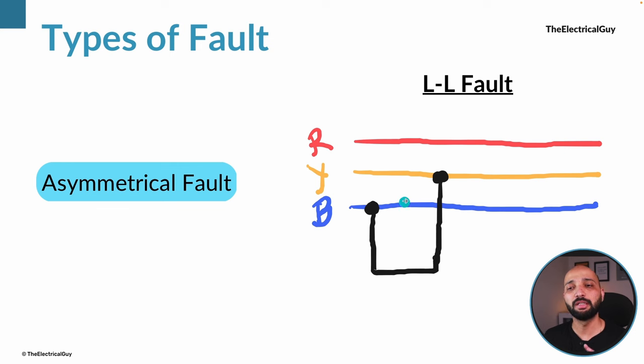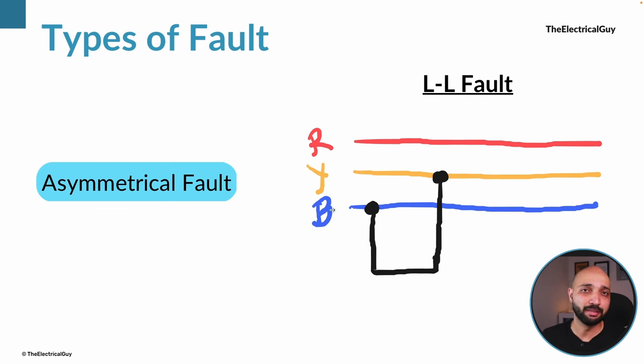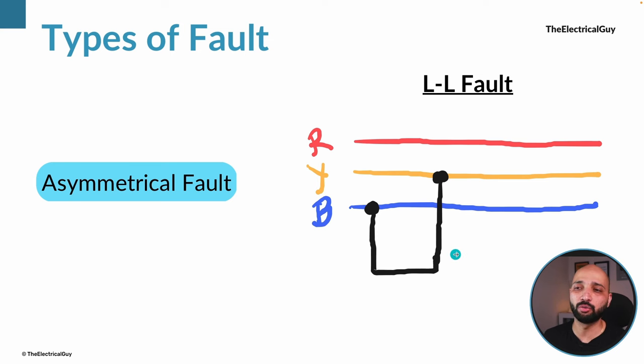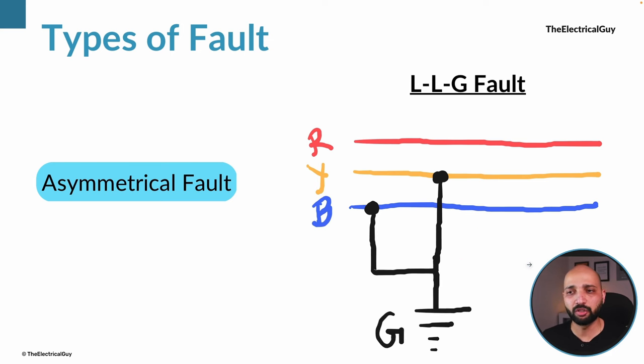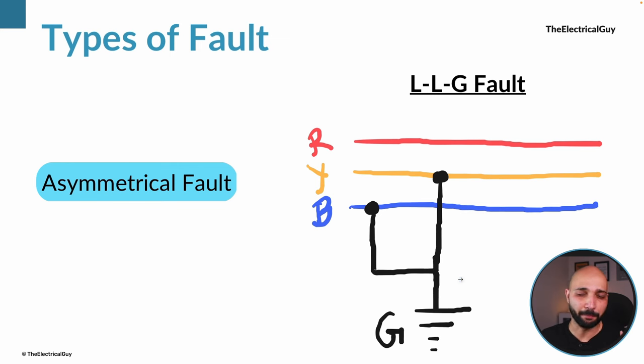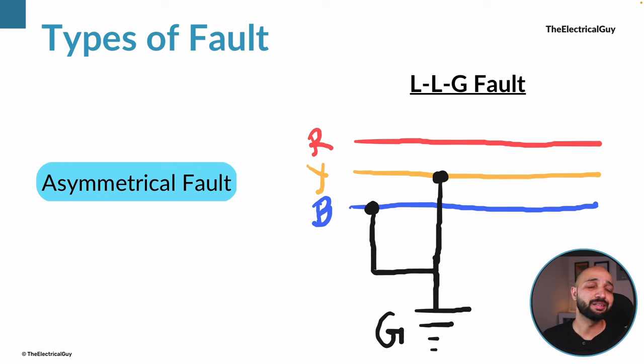There is also the double line fault, where Y phase and B phase are connected together. R phase remains healthy while Y and B are not, so the current flowing through all three phases will be different, resulting in asymmetry. There is also the double line to ground fault, where Y and B phases are connected together plus the ground is also in the picture. All of these are asymmetrical faults — the positive and negative half cycles are not equal, causing asymmetry.